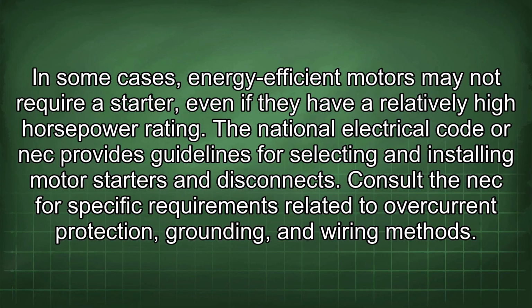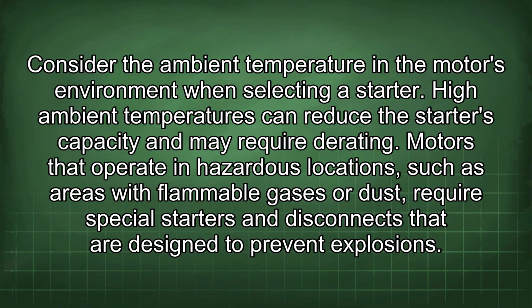The National Electrical Code or NEC provides guidelines for selecting and installing motor starters and disconnects. Consult the NEC for specific requirements related to overcurrent protection, grounding, and wiring methods. Consider the ambient temperature in the motor's environment when selecting a starter. High ambient temperatures can reduce the starter's capacity and may require derating.